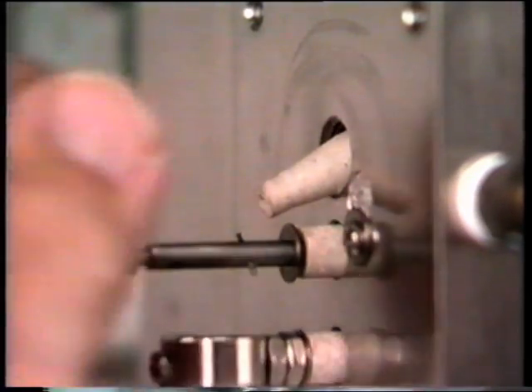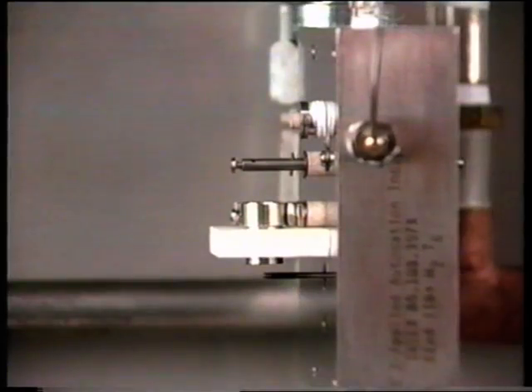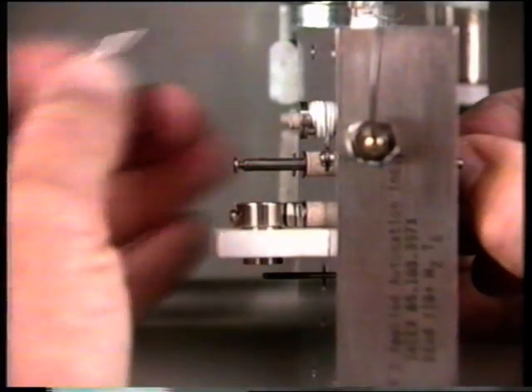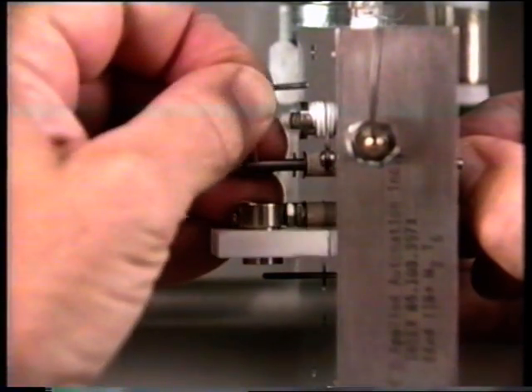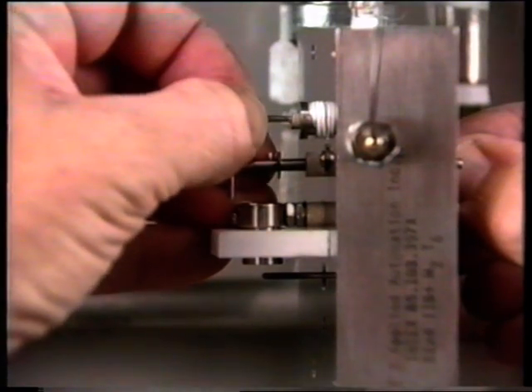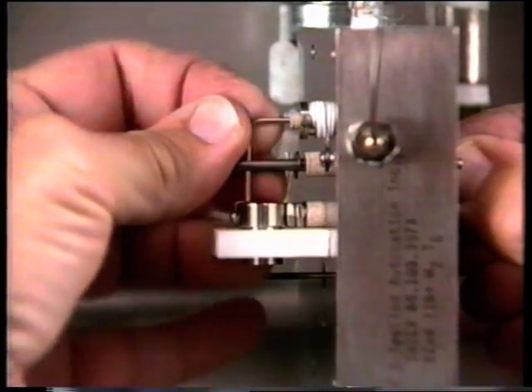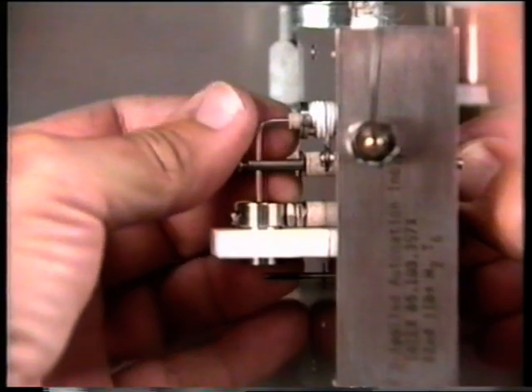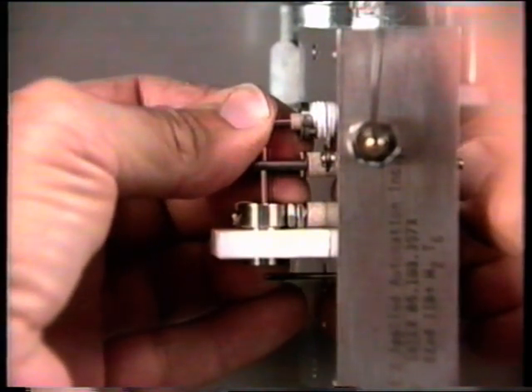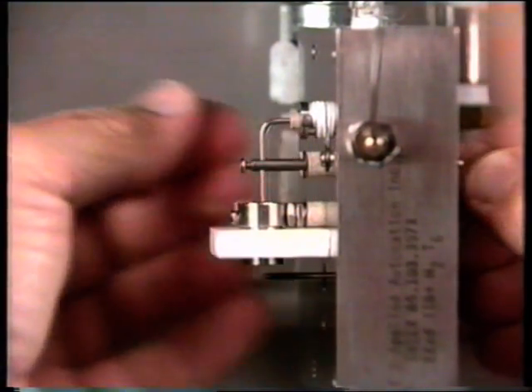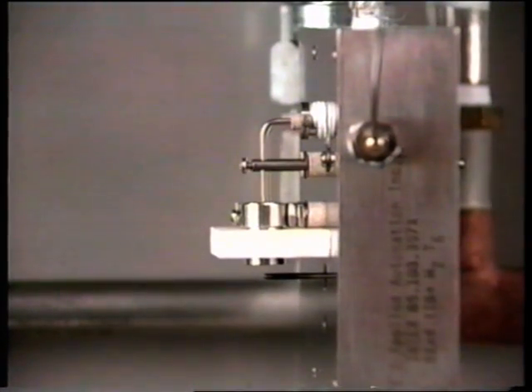Insert a new burner tip ferrule in its cavity in the detector body. Install the burner clamp nut over the ferrule and finger tighten it enough to hold the ferrule in place. Insert the long end of the burner tip through the hole in the bias ignite electrode. Align the short end of the burner tip with the hole in the end of its ferrule. Push the burner tip and the bias ignite electrode toward the body until the long end of the burner tip is centered over the collector and the short end is pushed into the ferrule.